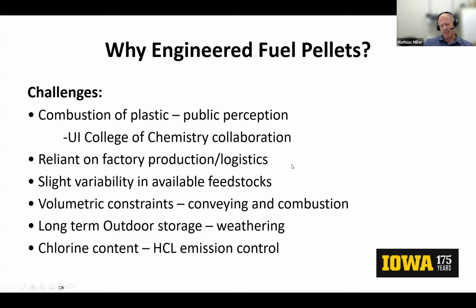We determined we were able to get high enough load out of the boiler. We took a moderate hit on boiler capacity, but weighed that against the additional capital to put new feeders on the boiler and determined it wasn't worth it. We just took a slight reduction in rated capacity and went with it. So that's something to think about—volumetric constraints.